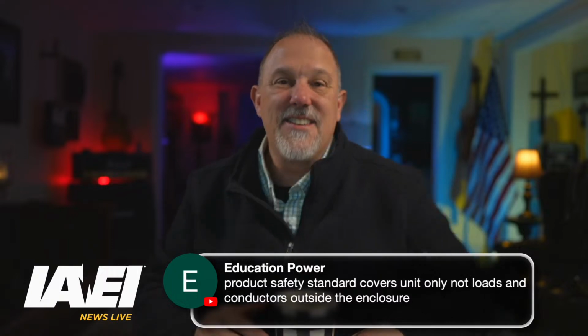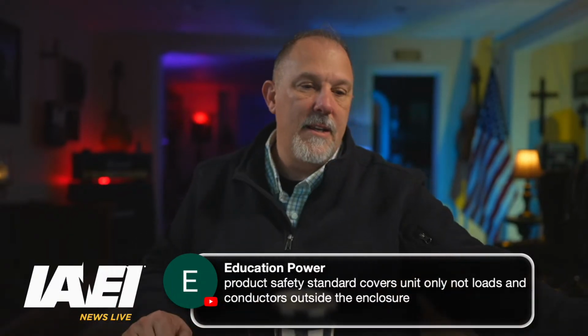I love this. So, Felix, the title of 240.5 is Protection of Flexible Cords, Flexible Cables, and Fixture Wires. It says flexible cord and cable shall be protected by an overcurrent device in accordance with their ampacity as specified in Table 400.5(A)(1) and 400.5(A)(2). Fixture wire shall be protected against overcurrent in accordance with its ampacity. Supplementary overcurrent protection as covered in 240.10 shall be permitted to be an acceptable means for providing this protection.